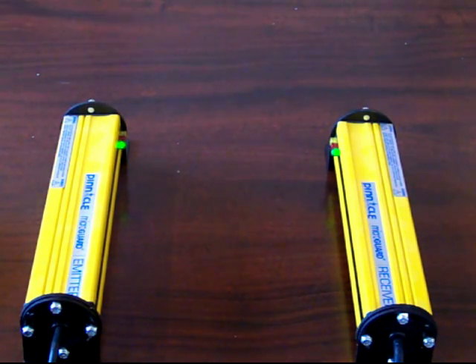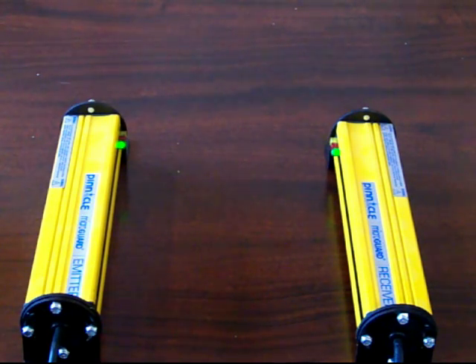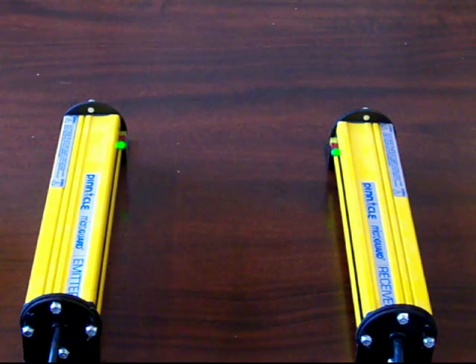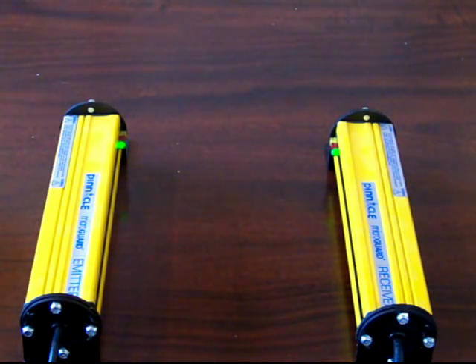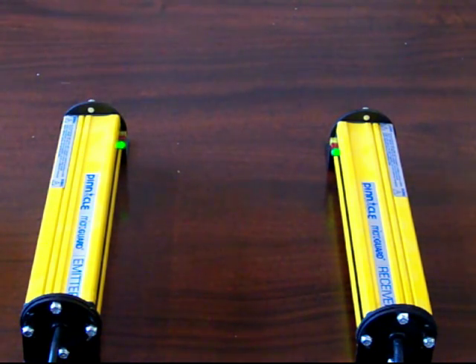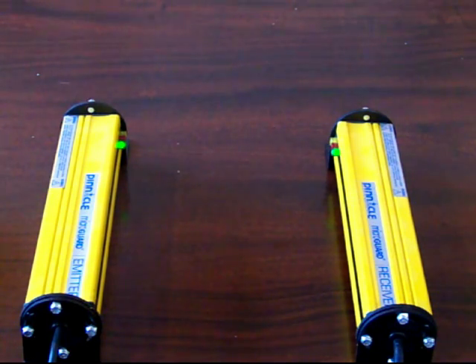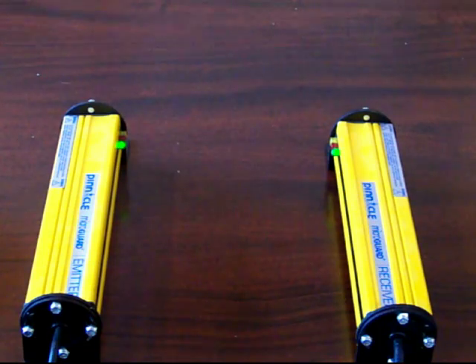That's the white and green wire. If you were to disconnect the white and green wire, you go into a bottom beam sync mode rather than a sync through the data network. This allows you to free up the emitter pylon, power it from another source, and connect it at a different point. The only downside is you cannot run blanking and block the bottom beam at any time. Otherwise, you lose your blanking.